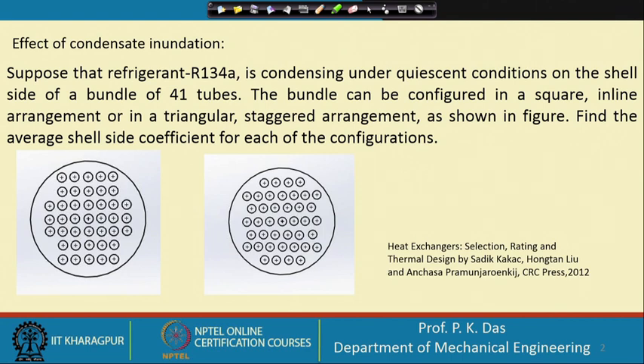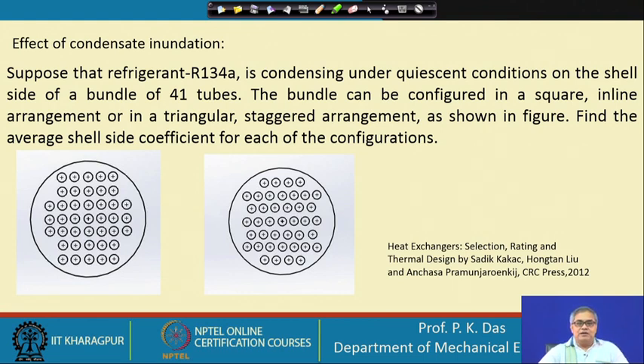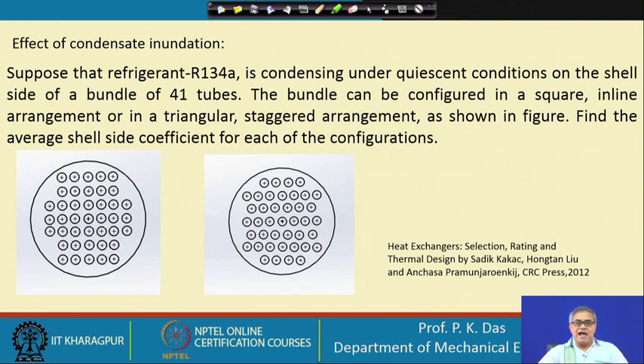Here all the tubes will take part in condensation, but the condensate from the tube above will fall on the tube below, which will thicken the condensate film of the tube below and diminish the rate of heat transfer. This diminishing effect is a progressive one — as we go to tubes lower and lower, there will be a more detrimental effect of film flooding. This we have to take into consideration, and the average heat transfer coefficient must be estimated accounting for all the heat transfer coefficients on the different tubes.